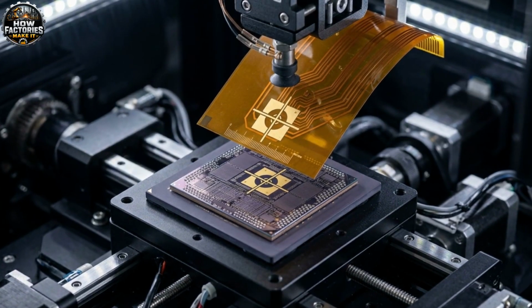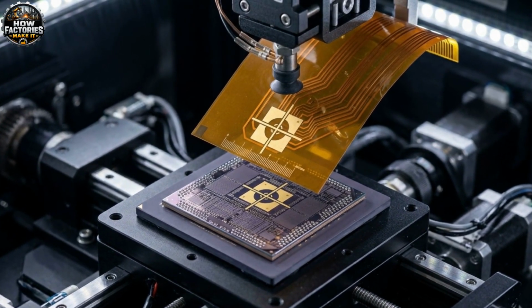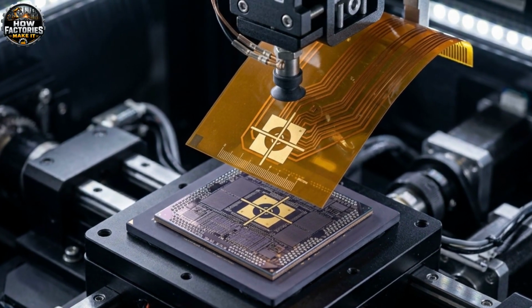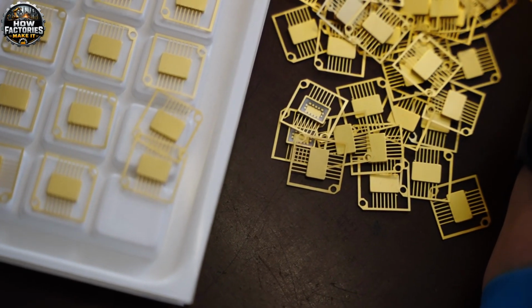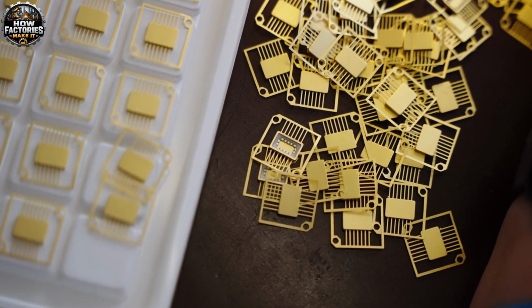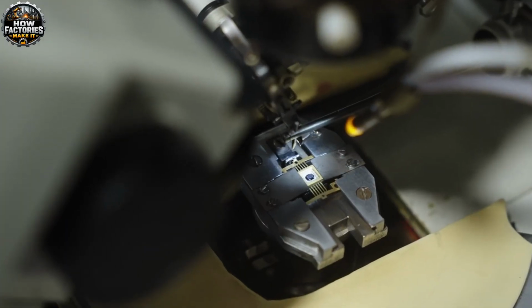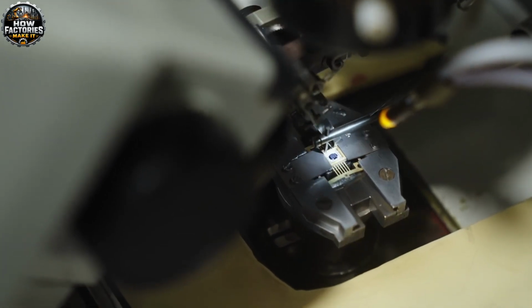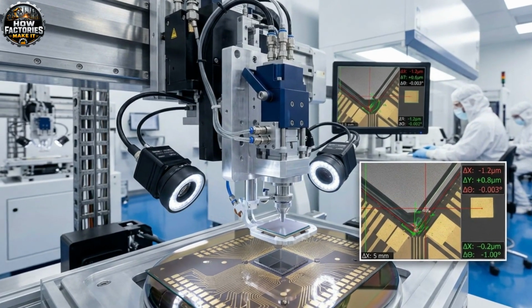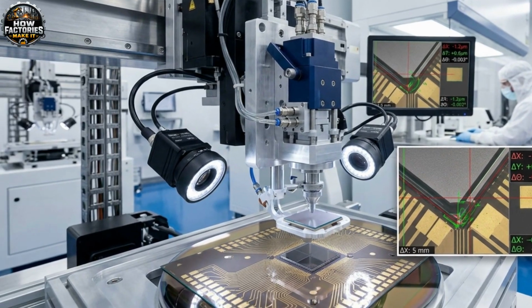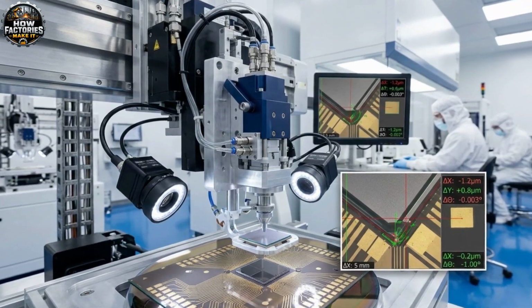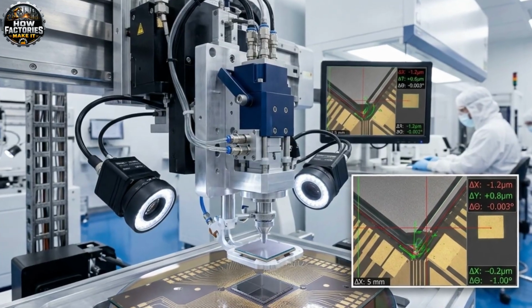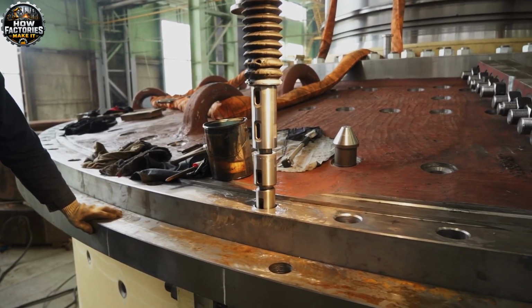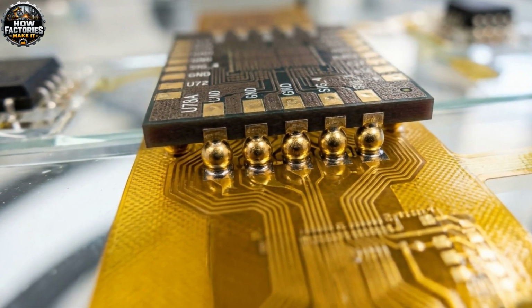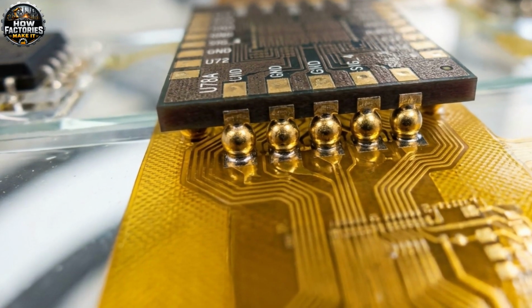The sensor end of the thin film array contains microscopic contact pads corresponding to the recording channels. The custom processor chips must be aligned precisely with these contacts. A method known as flip chip bonding can be used for this operation. The processor die is turned face down and positioned above the matching contact area. Machine vision cameras examine alignment marks on both components. The placement system makes tiny corrections until the contacts are aligned. Controlled heat, pressure, or ultrasonic energy then creates the electrical connection.